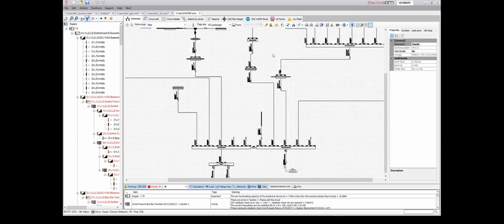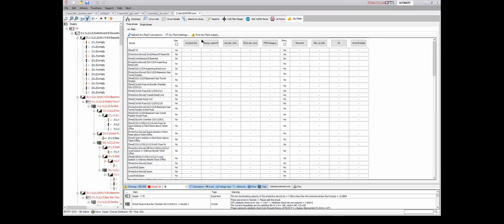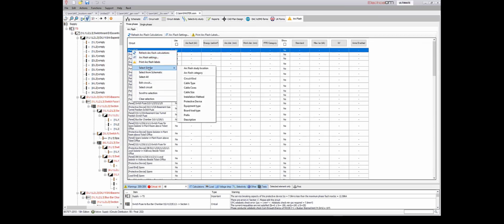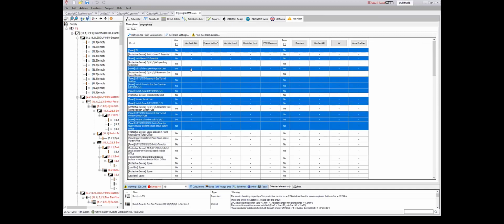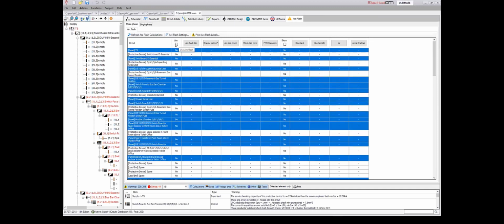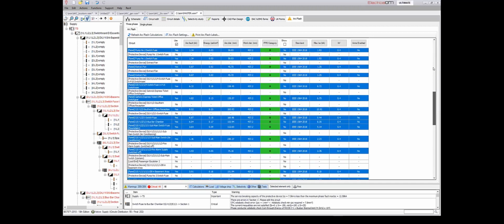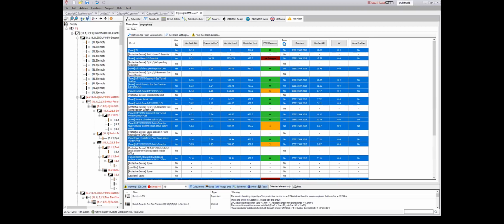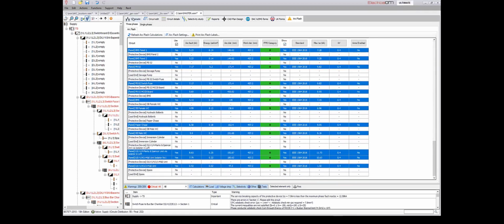And then after navigating through the arc flash component here, you can choose a location. So the location is stated at the prefix of each description. So this is the panel, this is a protective device, this panel, and so on. So usually you're going to perform an arc flash assessment on each panel. So I'm going to right click on that, select similar, and then select arc flash study location. Then what I will do, I will choose to use the arc flash study for each location. Okay, the software already performed the arc flash study for the selected locations, and then I will choose to show this on the network, on the schematic diagram.